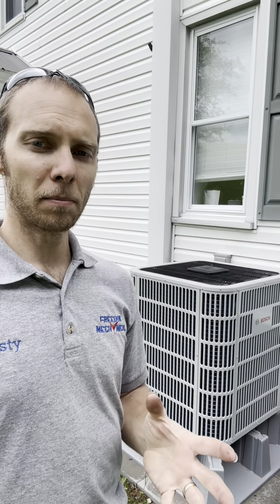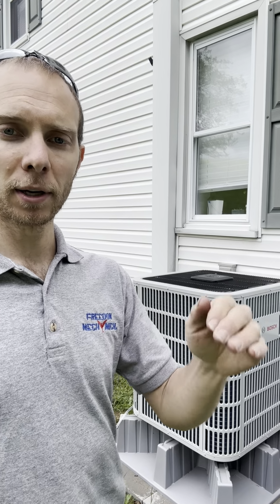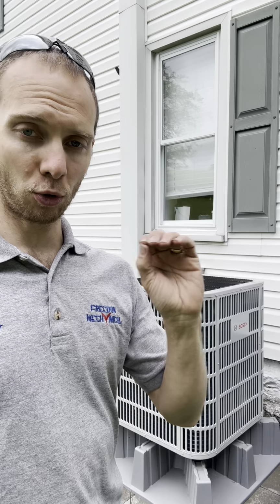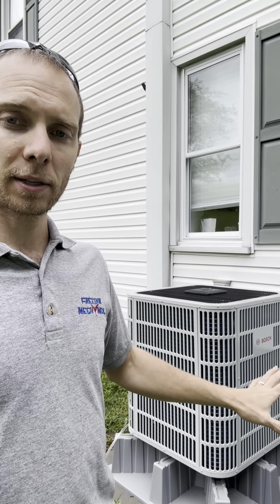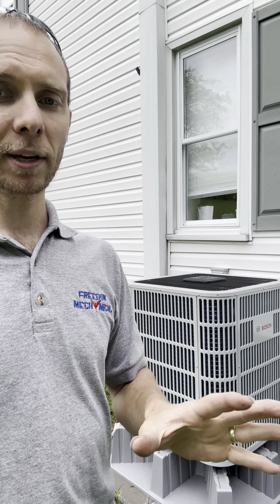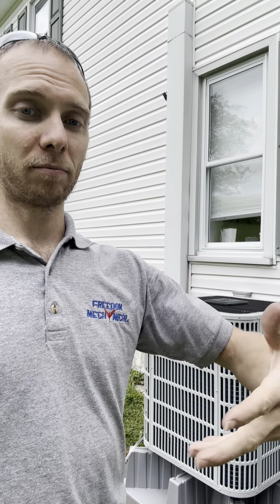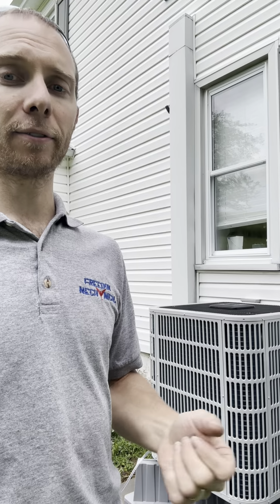So when we engage the heat mode in our Bosch heat pump, every Bosch heat pump does the same thing regardless of which tier you bought. When you call for heat at the thermostat, there is a small delay, but then it's going to come on with just the fan. That's going to happen for about 30 seconds to 45 seconds. Then it's going to run air conditioning. It's going to do a predetermined defrost cycle before it ever generates heat. So between fan and defrost, before every single cycle, it's going to run for about a minute and a half, sometimes 2 minutes if you're timing it or something of that nature. So for 2 minutes, you're technically not going to get heat out of this unit.